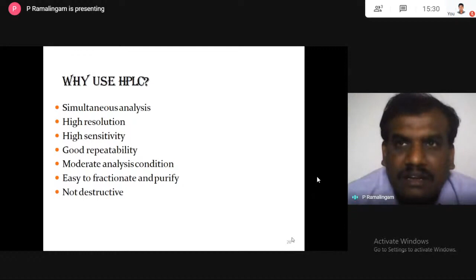So to handle HPLC, we don't require very stringent conditions, but we require a minimum of air conditioning and environment to handle the HPLC, to make the HPLC system a rugged one, easy to fractionate and purify, and it's not destructive. As I told you, whether it is destructive or not depends on the detector. Remember, in LCMS, the separation is not destructive. The detector is the one that determines whether your analysis is destructive or not. If you use a UV detector, it is not destructive. But if you use a mass detector, it is a destructive technique.